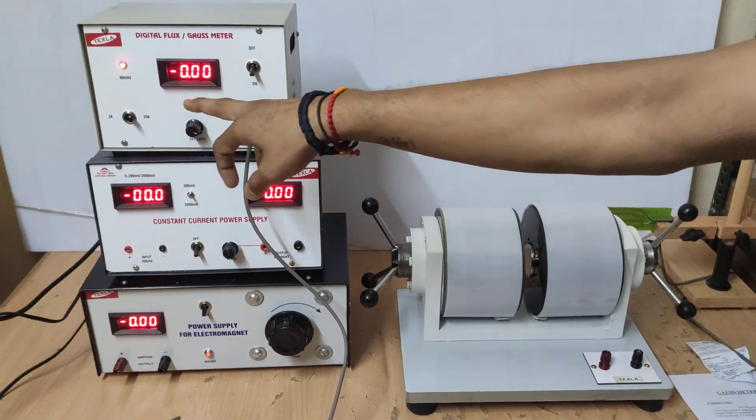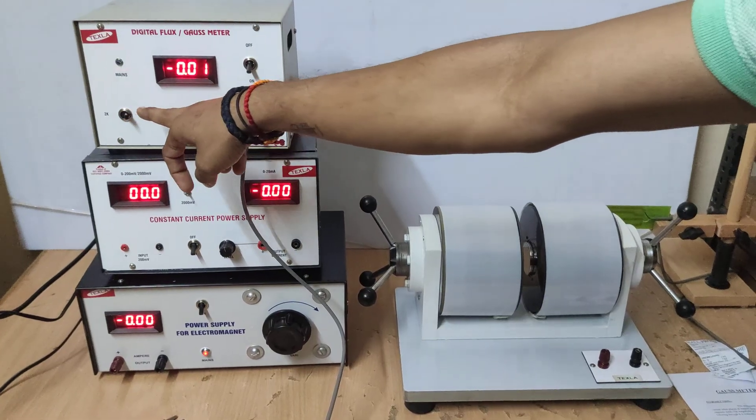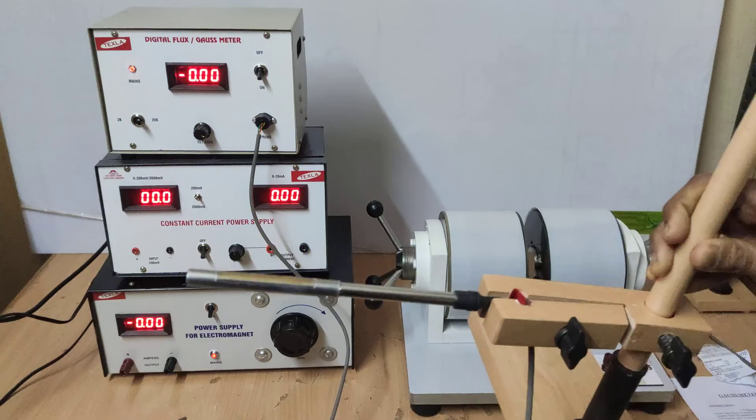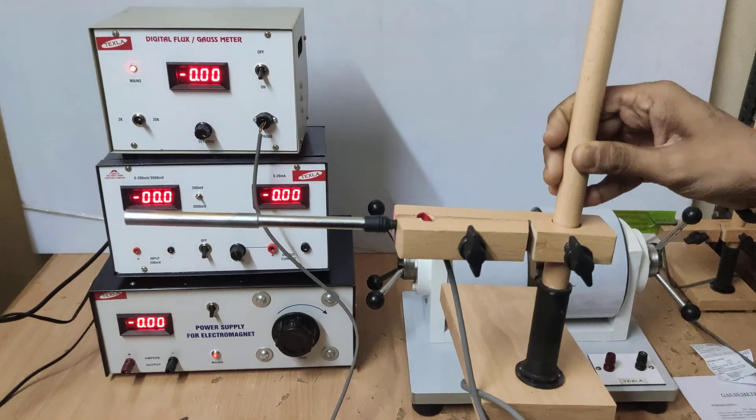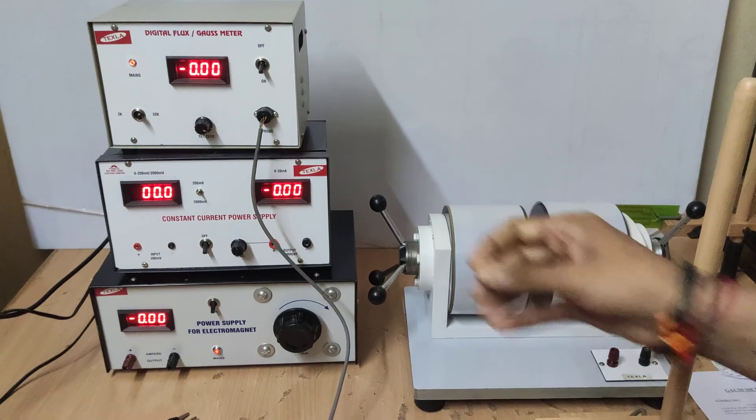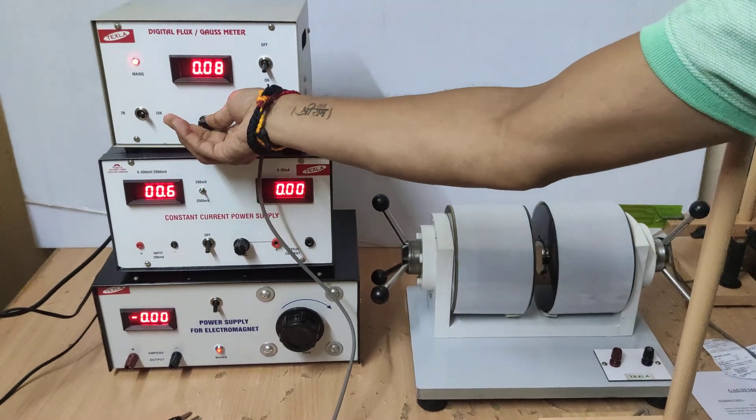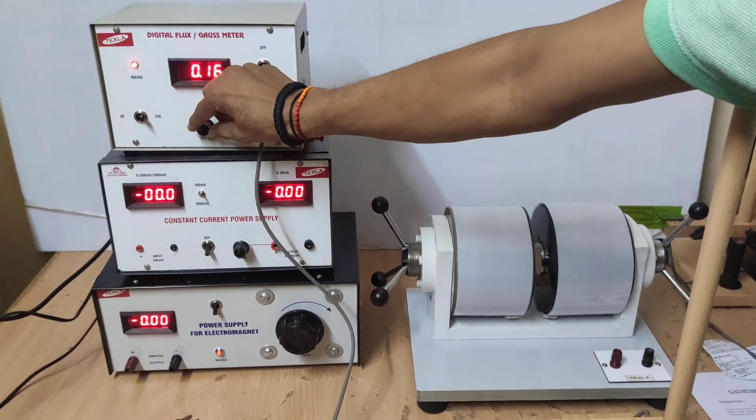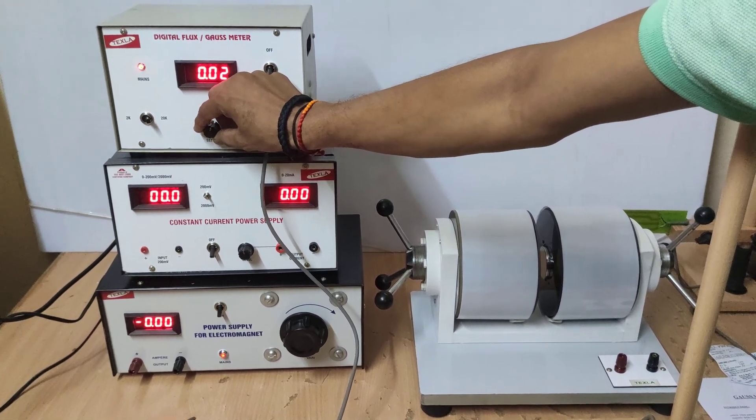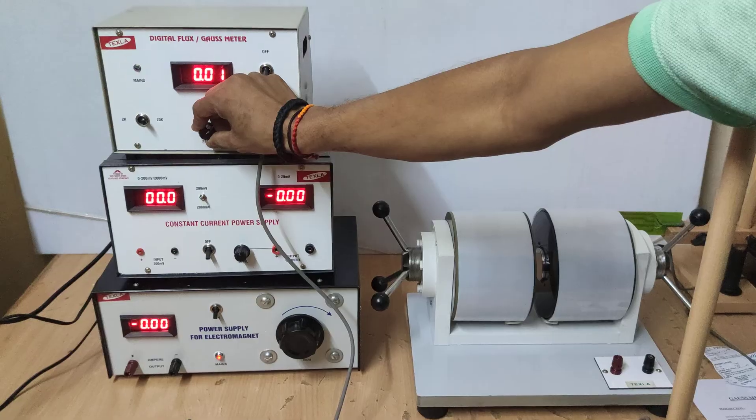The gauss meter is a digital gauss meter which has two different ranges, 2k and 20k, with a probe and provided with a wooden stand. Initially we need to set the gauss meter to zero by this knob. We need to set it to the zero option so that there is no error. With this knob I am setting it to zero.